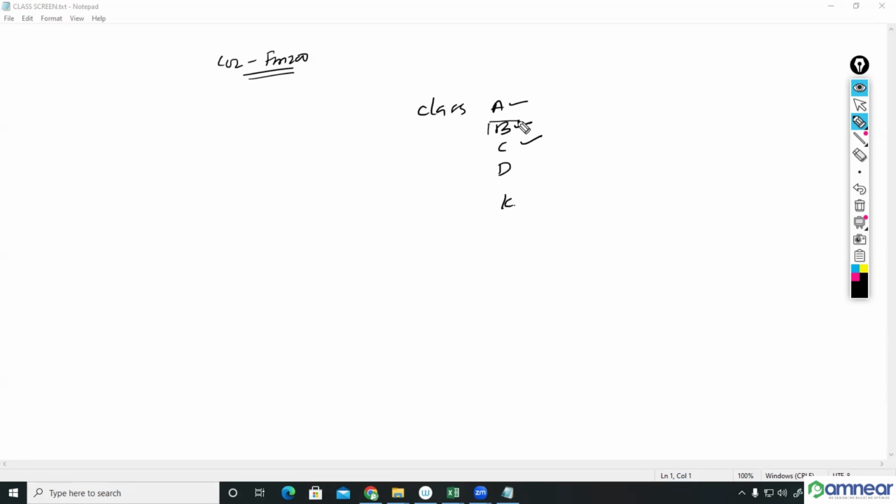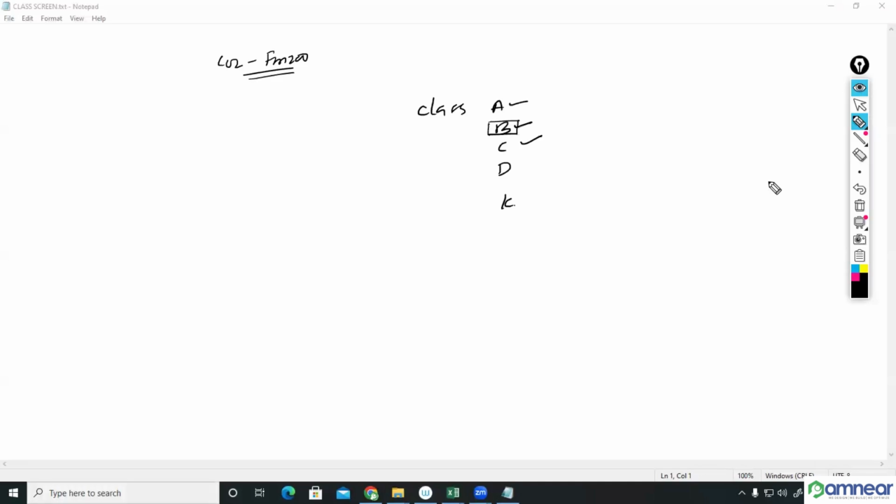Especially in class B, you can't use water. If you use water, the density of water is higher than petrol or diesel, so the less dense fuel will rise upward while the water flows down. It will be difficult to extinguish the fire, because the extinguisher can't create a layer above the fire surface. That's why for class B fire, you can't always use water.